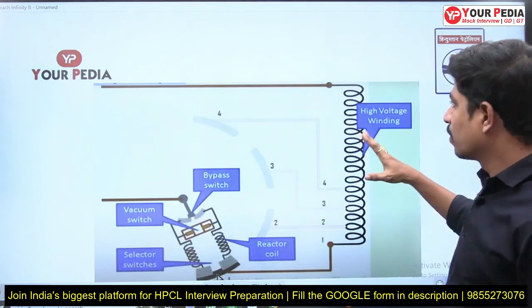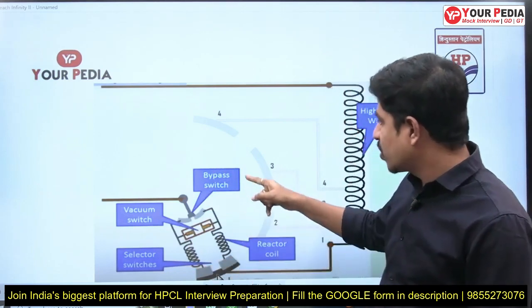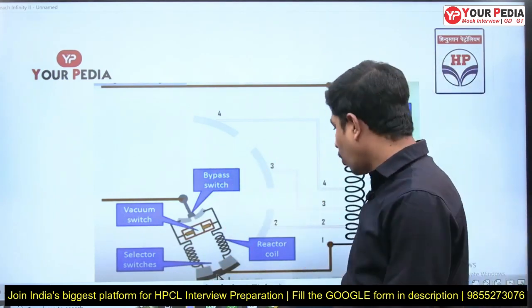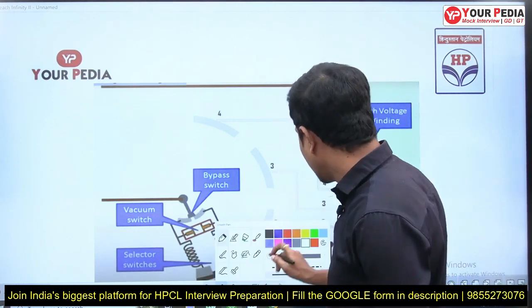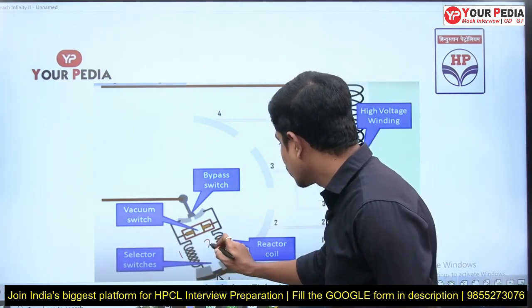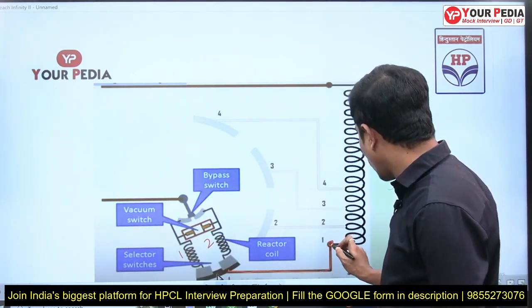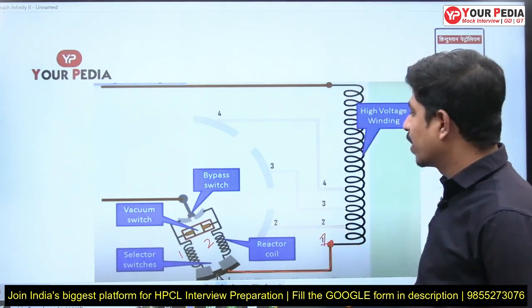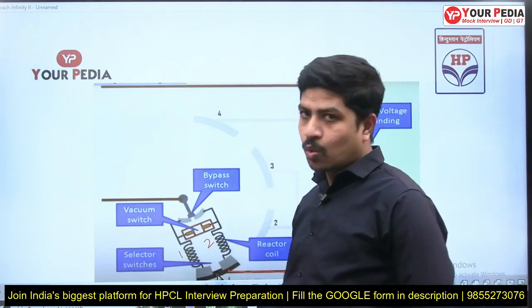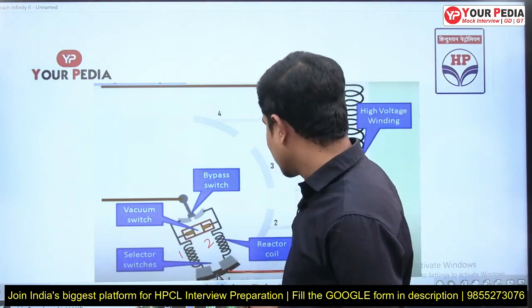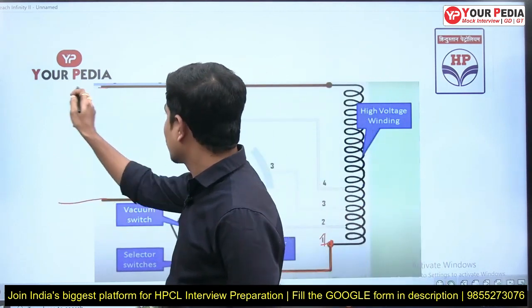This schematic is sourced from Google. This is the HV side on-load tap-changing schematic. There are two coils — I'll name them coil 1 and coil 2. Presently, the total winding is connected at position 1 on the primary. There is a vacuum switch, there are two selector switches, and there is a bypass switch. The two selector switches are connected to the supply.